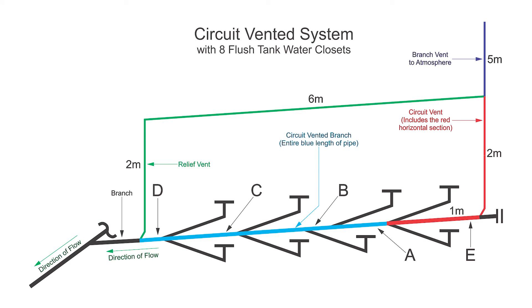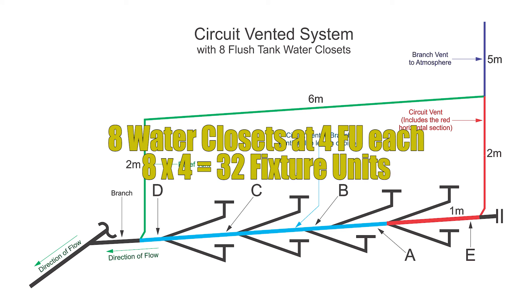It is finally time to size the circuit vent, but before we can do that we need to know a couple of things. First, the fixture unit load — that's easy. We have 8 water closets at 4 fixture units each, giving us 32 fixture units.